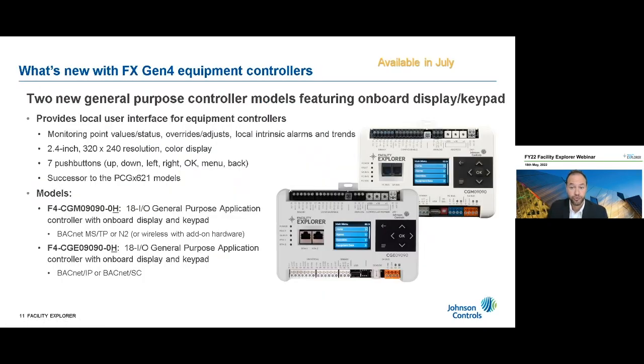Next, we have two new general purpose controllers with integrated or onboard display and keypad that will be available in July. They provide a local UI for controllers in a very intuitive way. Through the controller display, we can monitor points, check overrides, adjust set points, and also view alarms and trends, which wasn't there in the older version.